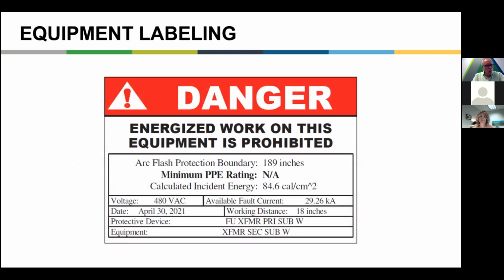And most companies across the country, when you cross the threshold above 40 calories, they just tell their workers, energized work is not permitted on this equipment. Look at the calories here, 84, 85 calories. Arc flash protection boundary, 189 inches. So at that distance away from the live parts, the worker could receive a second-degree burn if exposed. Scary.